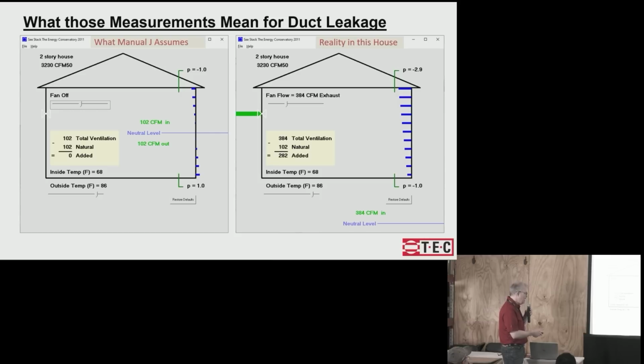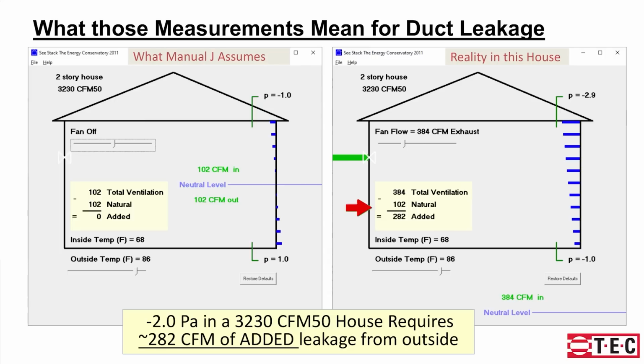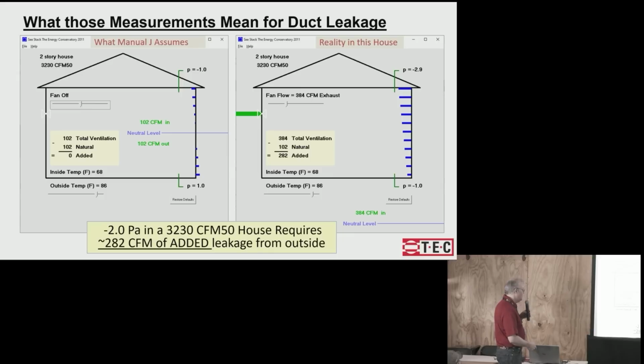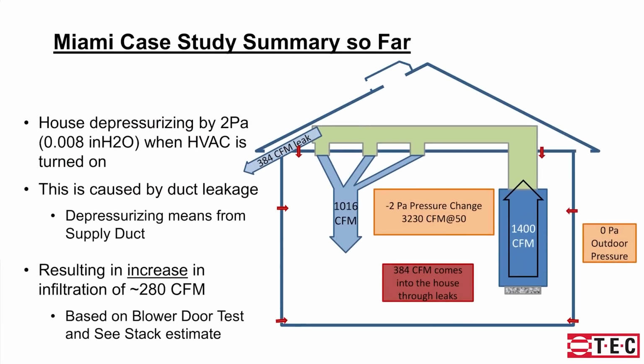Okay, so 384 CFM is what's really leaking. 102 is what we assumed in the Manual J. Even putting the correct blower door number in, this is what we assumed, because Manual J doesn't know that your supply duct is leaking out to the attic. So we assumed 102. We actually are leaking 384, so the difference is 282, right? That's how much extra leakage the Manual J calc is not accounting for. Let's talk about what that extra 282 is doing to us in the load calc.